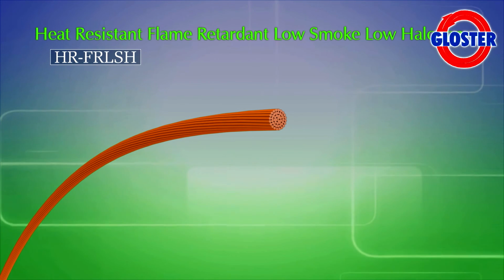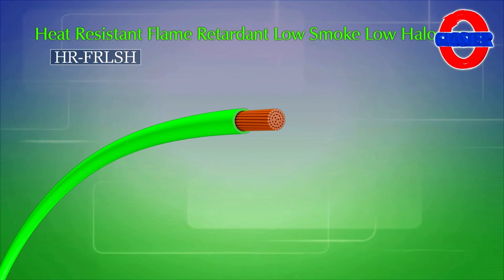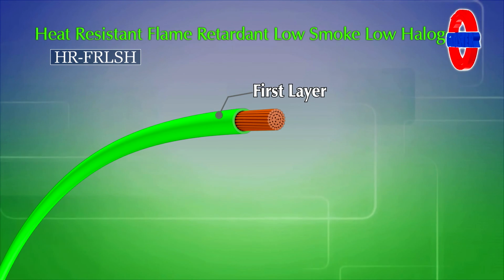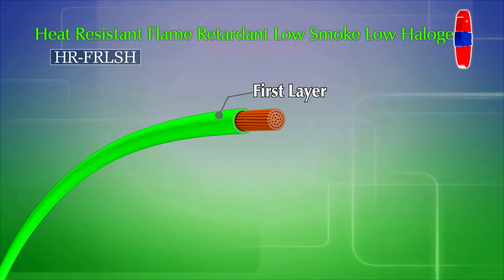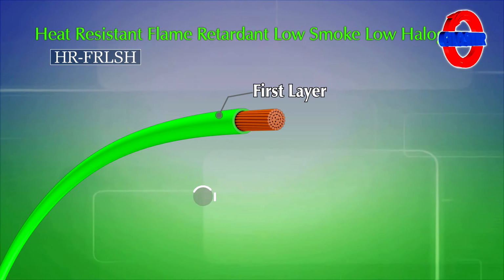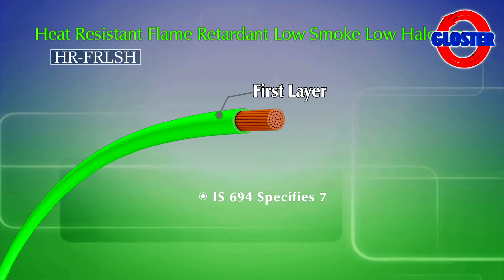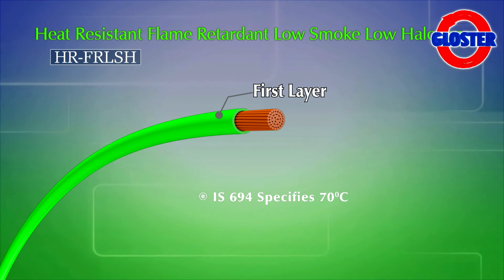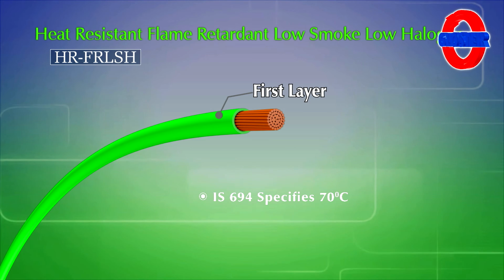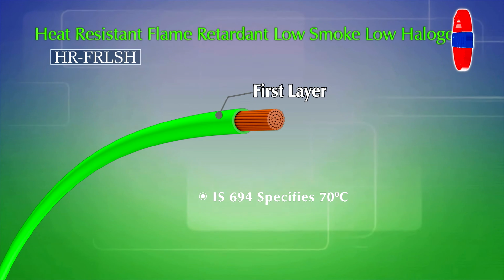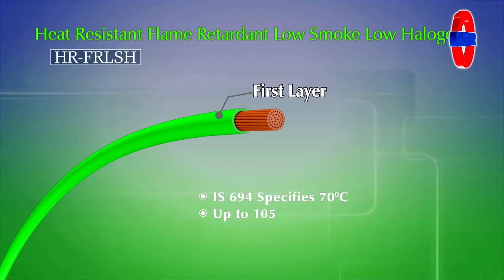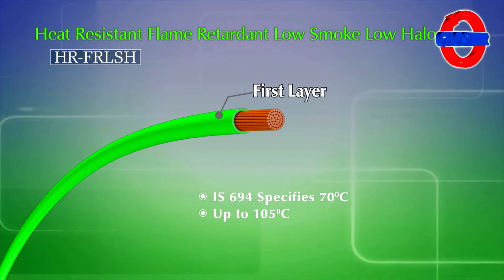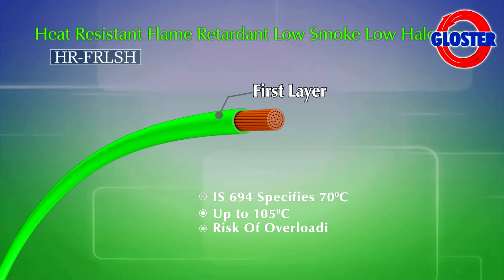Specially formulated in-house heat-resistant, flame-retardant, low-smoke, low-halogen insulation on first layer makes our wires handle higher temperatures and run cooler. IS 694 specifies 70 degrees Celsius continuous operating temperature. Our wires can operate way beyond 70 degrees Celsius up to 105 degrees Celsius short time, thus minimizing the risk of overloading and fire risks.